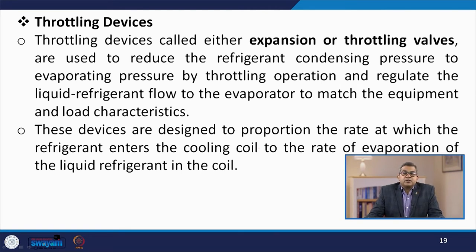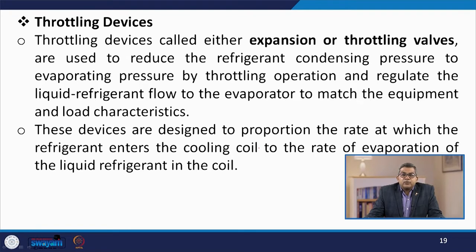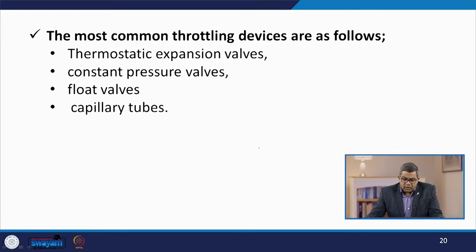Let us talk about the throttling device. Throttling devices are an integral part of any refrigeration system and are called either expansion or throttling valves. They are used to reduce the refrigerant condensing pressure to evaporating pressure by throttling operation and regulate the liquid refrigerant flow to the evaporator to match the equipment and load characteristics. These devices proportion the rate at which refrigerant enters the cooling coil to the rate of evaporation of liquid refrigerant in the coil. The most common throttling devices are thermostatic expansion valves, constant pressure valves, float valves, and capillary tubes.